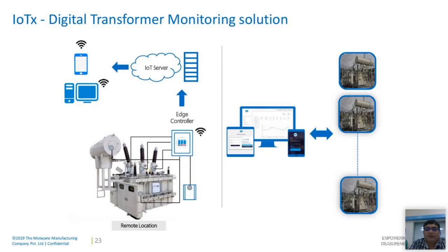So this data goes and sits in the database of the platform. The benefit we get is that if we see the offline testing data and the real-time operating data in isolation, there will be limitations in the analysis we can conduct. If we're looking at root cause analysis, it's important to understand both the patterns from periodic testing of the asset and the conditions under which the asset is operated.